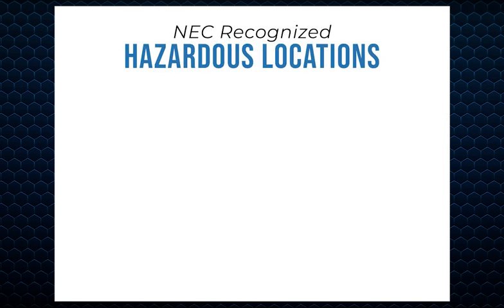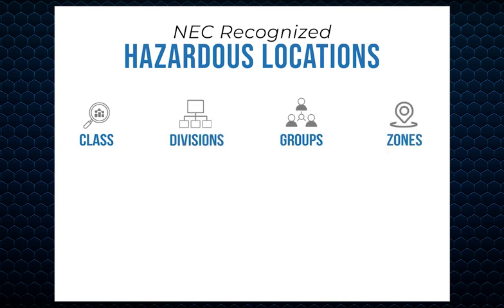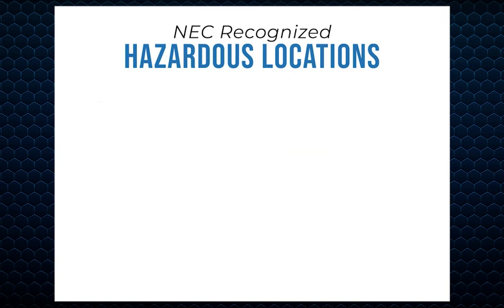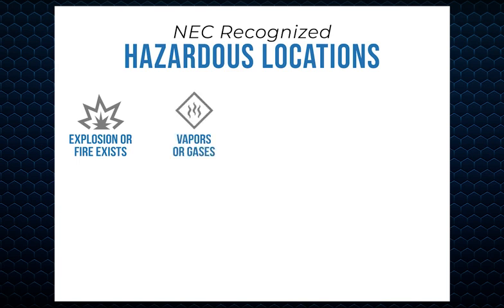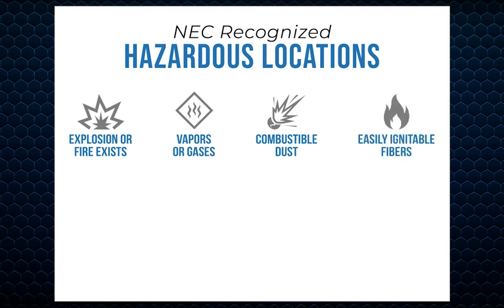Outer jackets contribute to a cable's hazardous locations rating. The NEC breaks hazardous locations down into class, divisions, groups, and zones. These classifications allow end users to better understand if the area they are working in is considered dangerous, so that proper cable types can be used for added safety. A hazardous location is an area where the possibility of an explosion or fire exists, which can be created by the presence of flammable vapors or gases, combustible dust, or easily ignitable fibers.